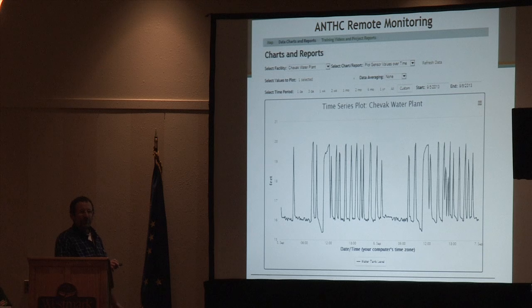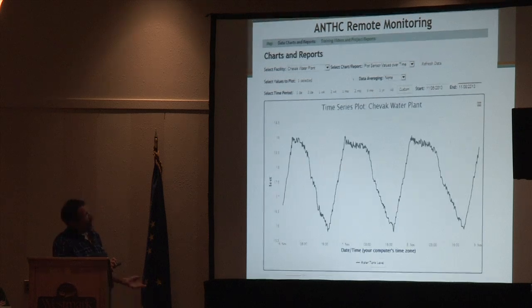What was happening was the pressure sensor was on the line going to the tank. So as soon as the pump kicked on to fill the tank, the pressure sensor would think the tank's full and turn off. This helped us find a problem we didn't even know existed. So we put a new pressure sensor out in the tank where the pump wouldn't affect it, and this was what it looked like after that. It's helping us identify things we didn't even know we had a problem with.